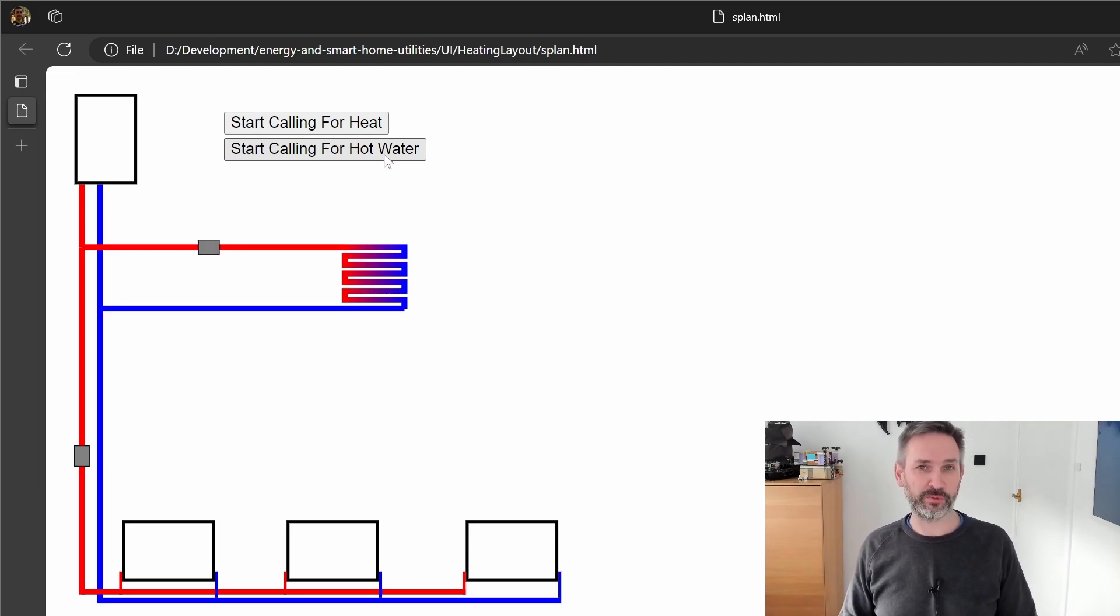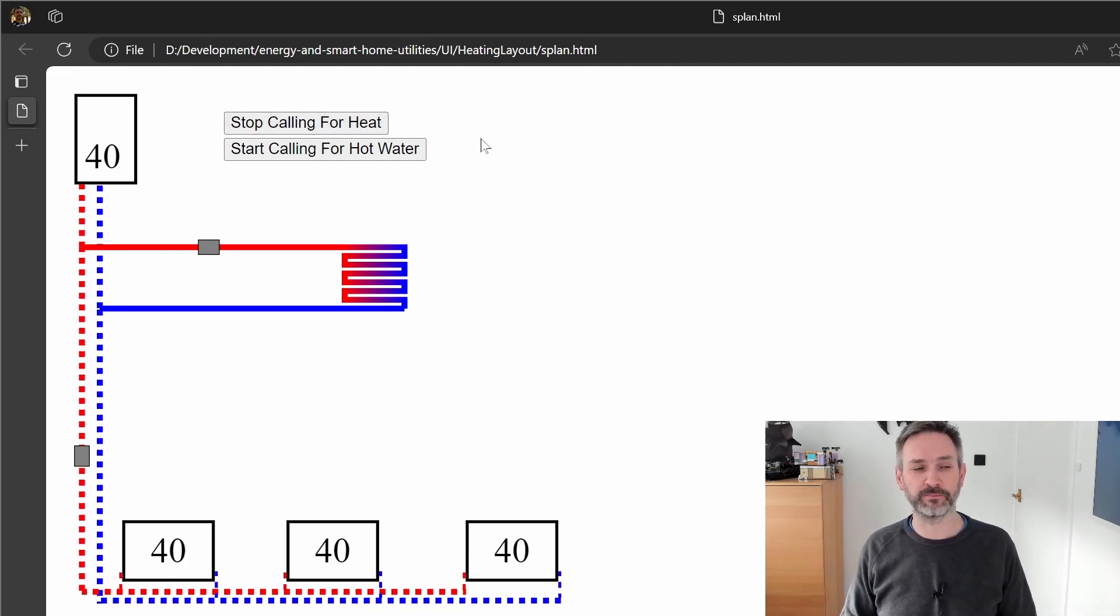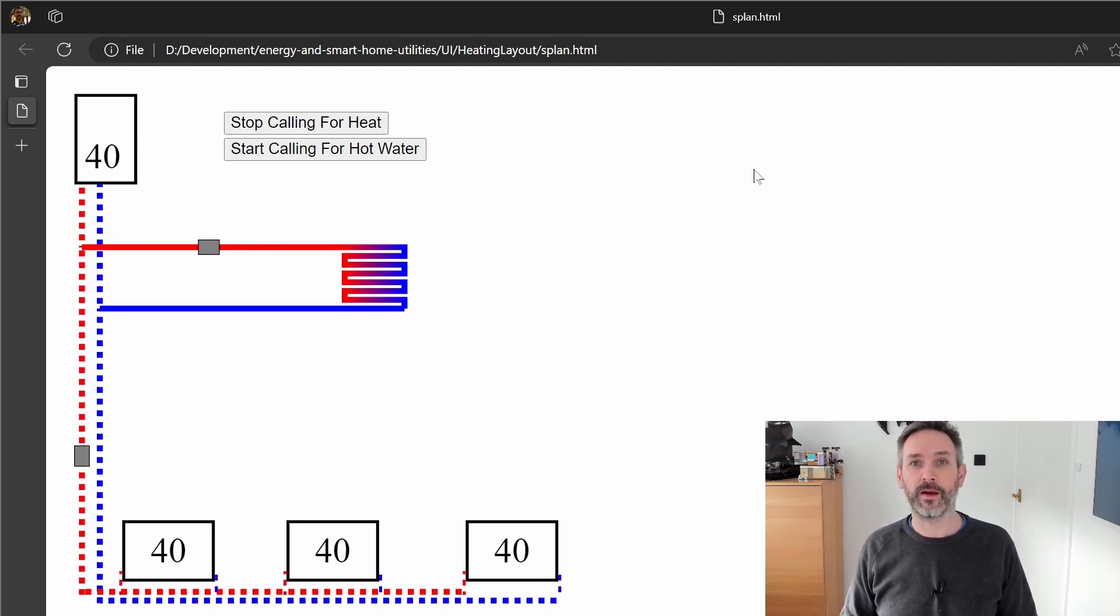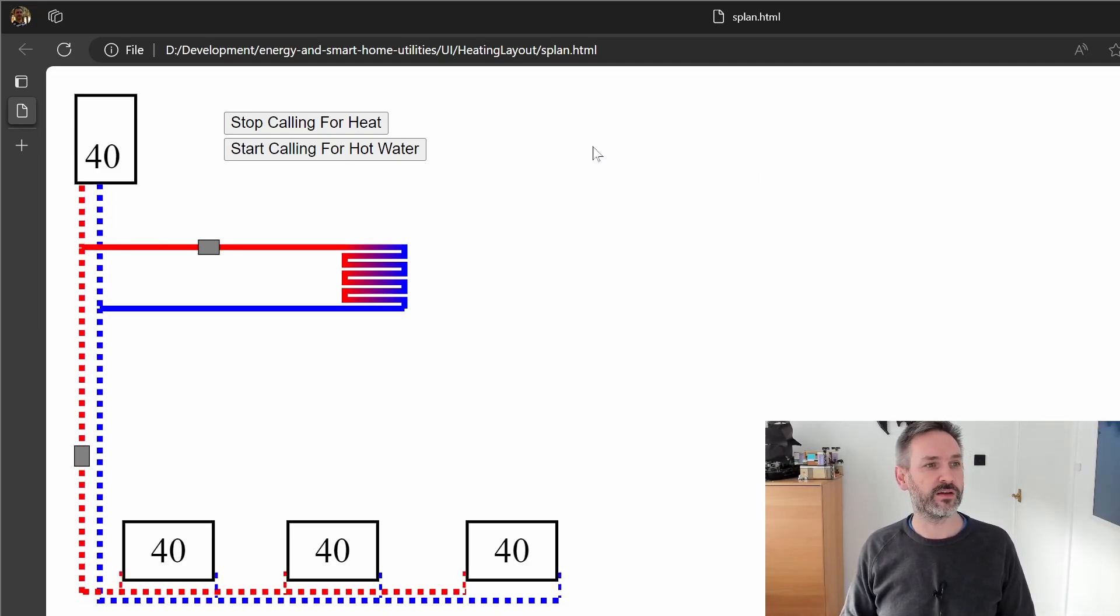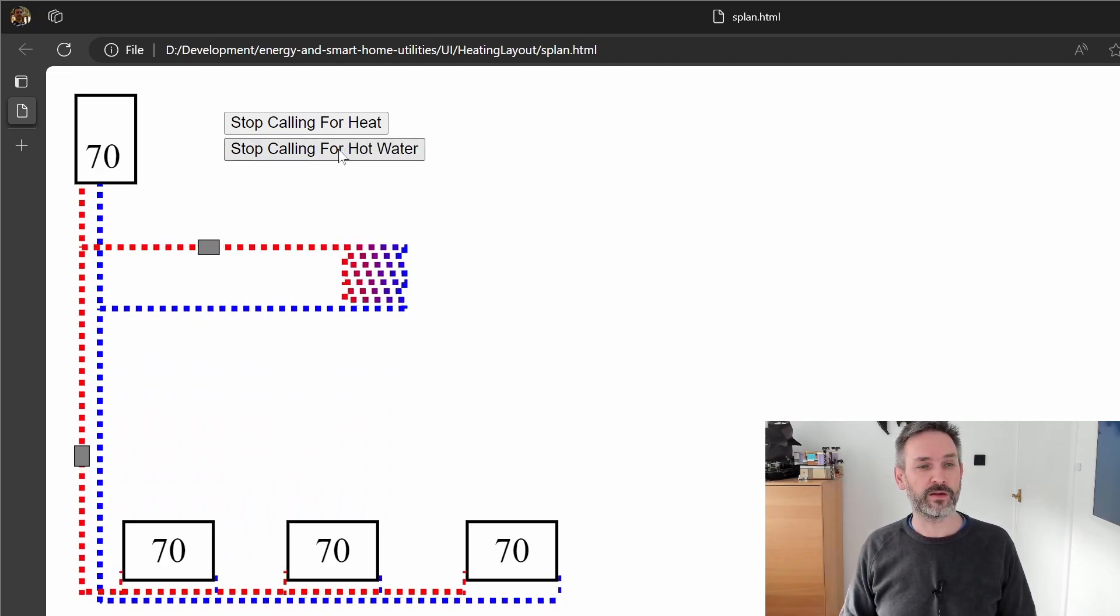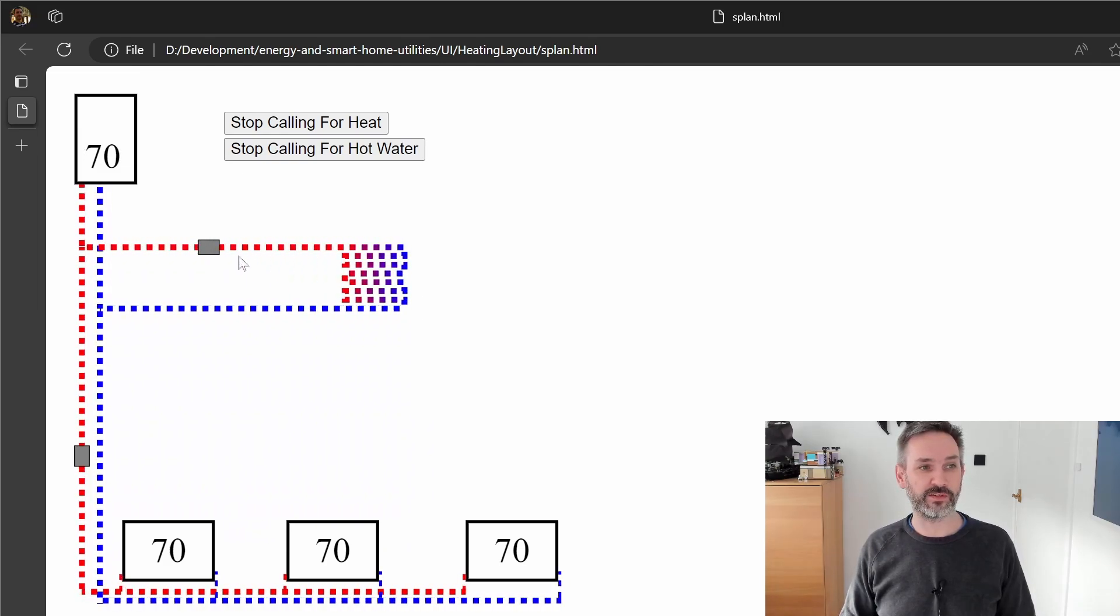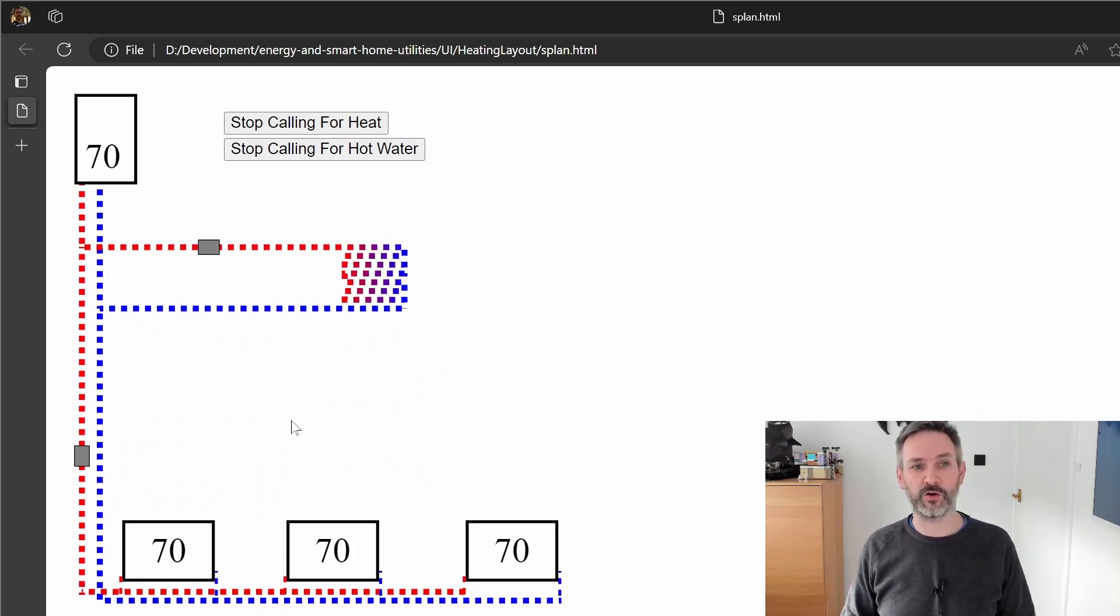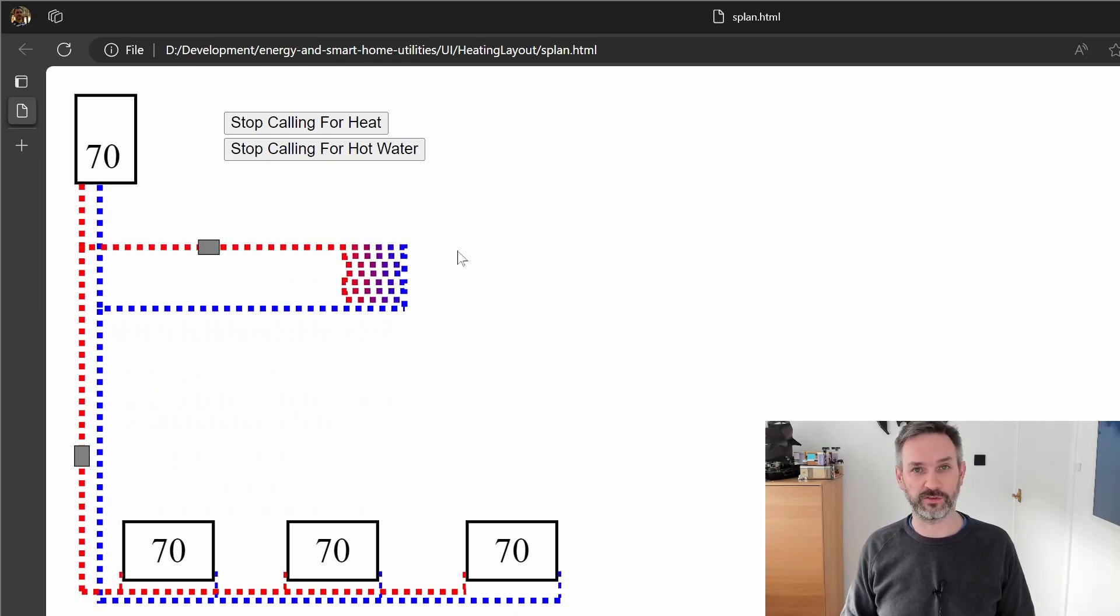So far so good. The problem arises when this happens: let's say the heating comes on early in the morning and our boiler is at 40 degrees happily circulating that water and then we need to boost the hot water in the tank because maybe we have some guests. What happens now is the boiler increases its flow temperature to 70, opens the zone valve for the coil but the zone valve for the heating has also stayed open so we're now circulating the water at 70 degrees around the whole house.